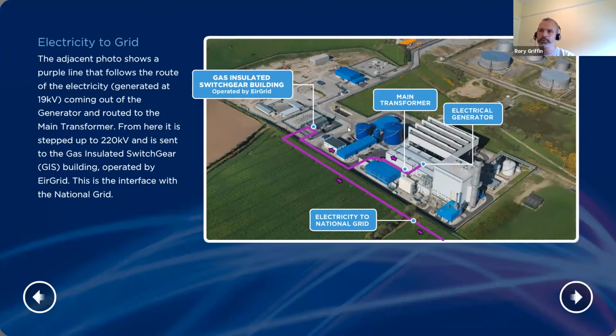I suppose one thing to point out: when Whitegate was first commissioned, it did have a temporary connection. So you had this compound here. This is air insulated switchgear, out in the open. Finally, when the GIS was commissioned, the connections were moved here, and this now is redundant. These are the original construction offices, and we still use these to this day. They're quite handy during maintenance outages because we've quite a lot of space on the site. As contractors come in, we can house them in different locations here, with canteen facilities, etc.